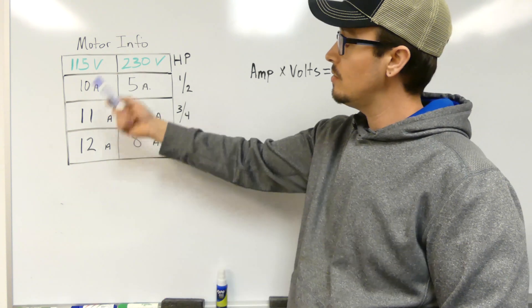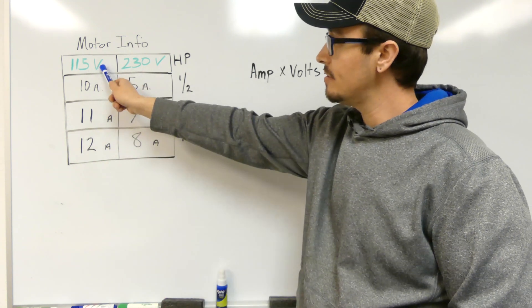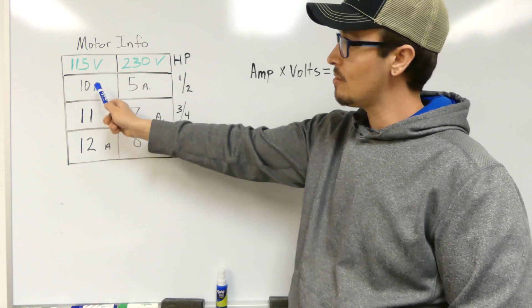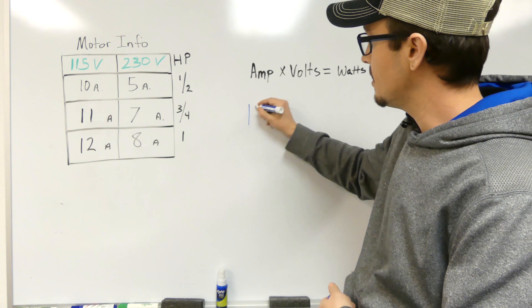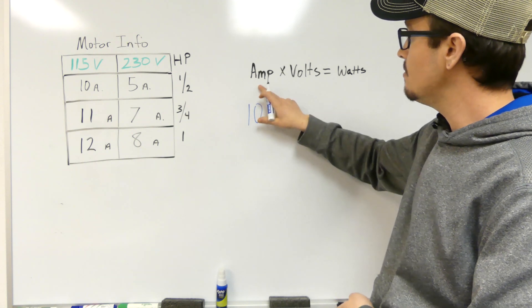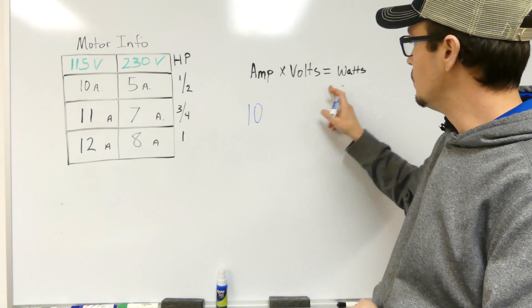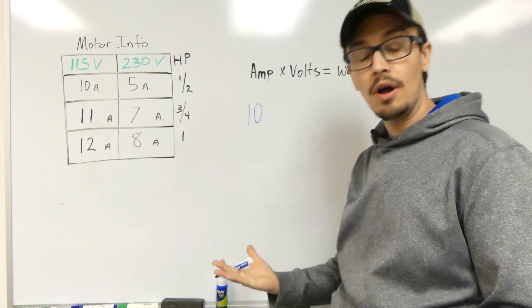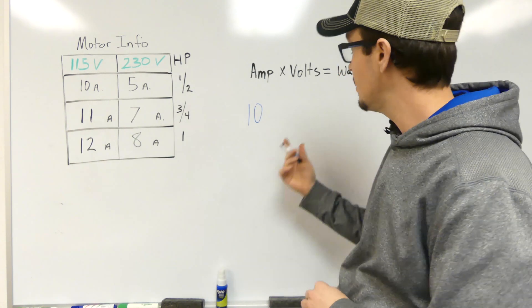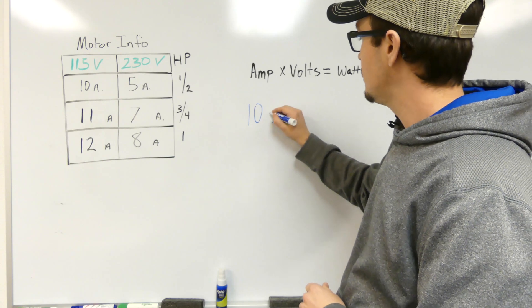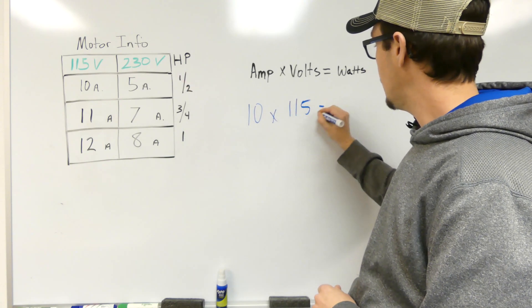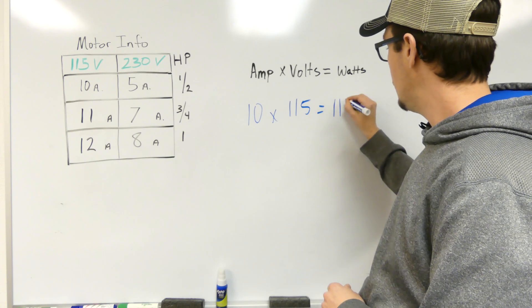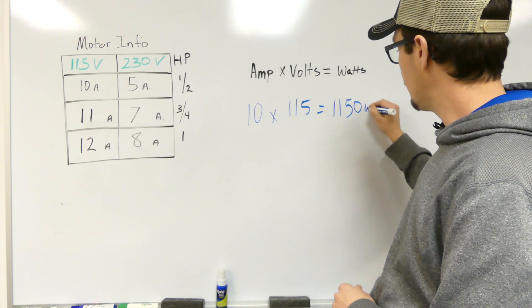So for our example, 115 volt half horsepower pump is at 10 amps, so we're gonna put 10 here because in our formula amps times volts equals watts. So times our volts, which is going to be 115, and we end up with 1150. So that's our watts.